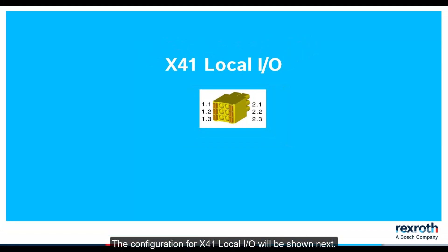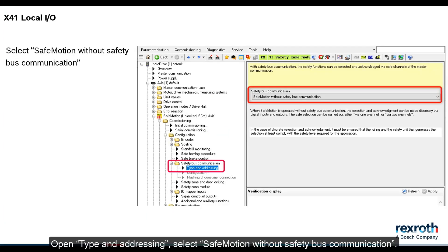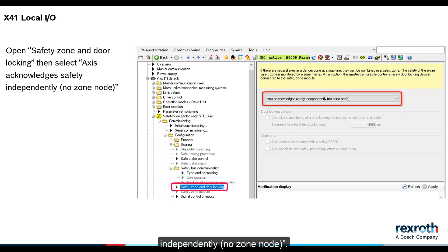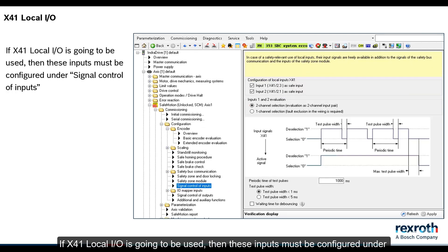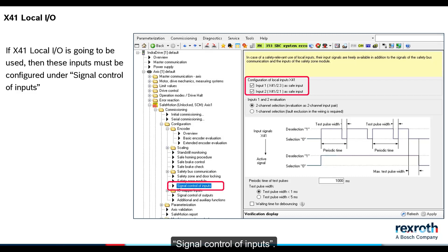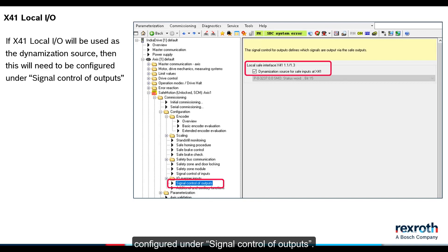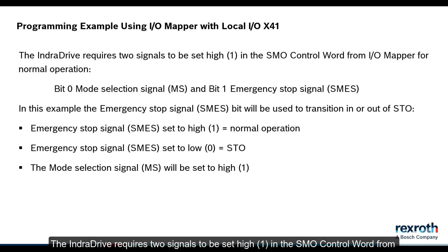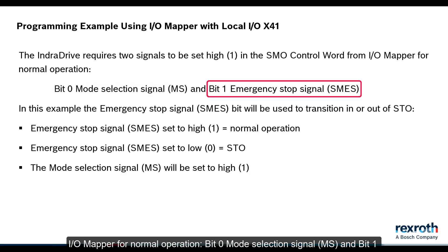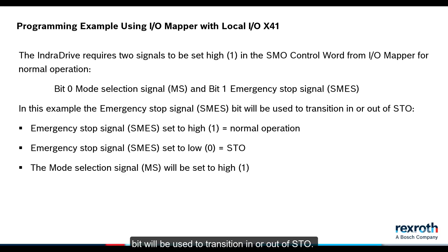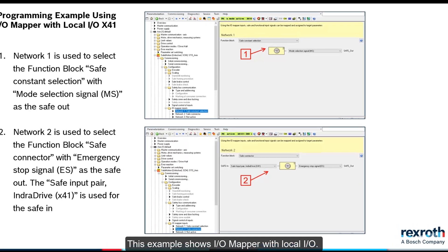The configuration for X41 local IO will be shown next. Open type and addressing. Select safe motion without safety bus communication. Open safety zone and door locking, then select axis acknowledges safety independently, no zone node. If X41 local IO is going to be used, then these inputs must be configured under signal control of inputs. If X41 local IO will be used as the dynamization source, this will need to be configured under signal control of outputs. The IndraDrive requires two signals to be set high in the SMO control word from IOMapper for normal operation: Bit 0, Mode Selection Signal MS, and Bit 1, Emergency Stop Signal SMES. In this example the SMES bit will be used to transition in or out of STO. This example shows IOMapper with local IO.